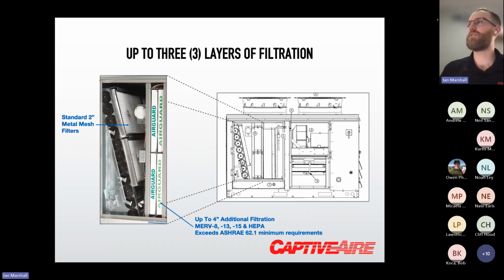For filtration, our standard filtration would be a 2-inch metal mesh on the outdoor air intake, followed by two 2-inch racks, so a 2-inch MERV 8 and a 2-inch MERV 13. Those two 2-inch racks can actually be replaced. We can do a single 4-inch rack. We'd have to order it this way from the start, but it can be a single 4-inch MERV 15, or a 4-inch HEPA is an option as well.